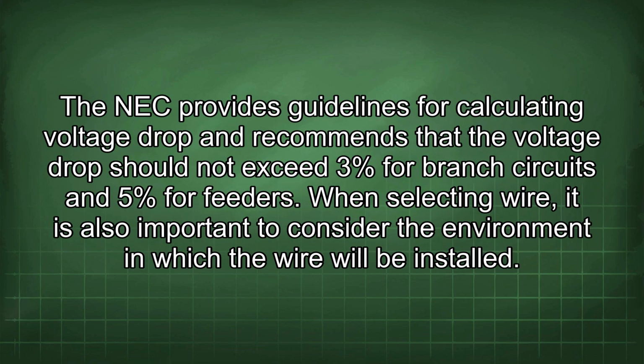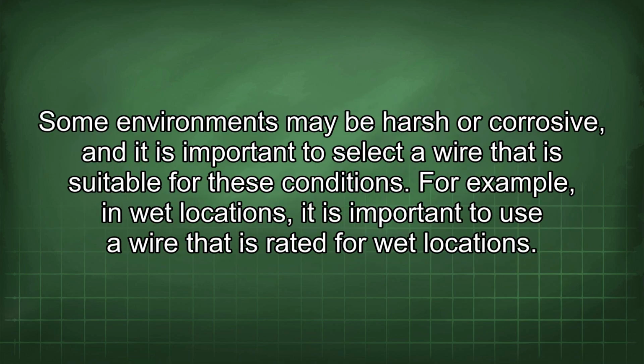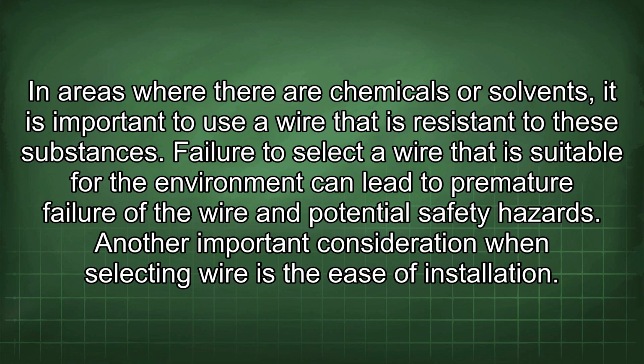The NEC provides guidelines for calculating voltage drop and recommends that the voltage drop should not exceed 3% for branch circuits and 5% for feeders. When selecting wire, it is also important to consider the environment in which the wire will be installed. Some environments may be harsh or corrosive, and it is important to select a wire that is suitable for these conditions. For example, in wet locations, it is important to use a wire that is rated for wet locations. In areas where there are chemicals or solvents, it is important to use a wire that is resistant to these substances.